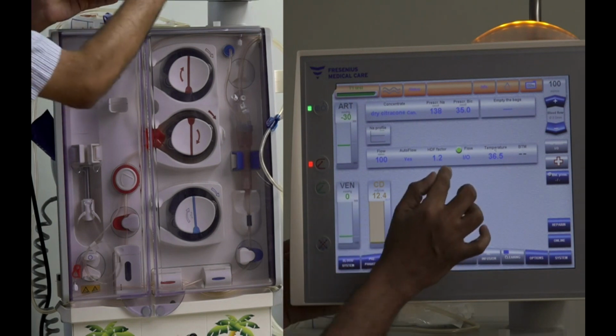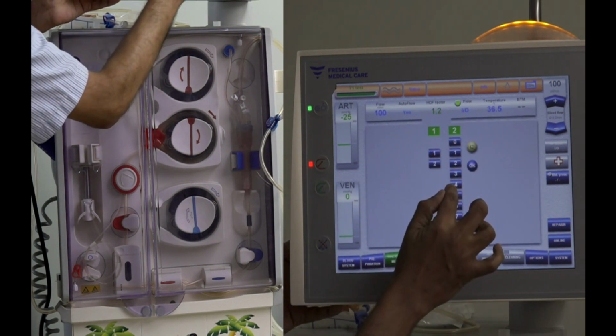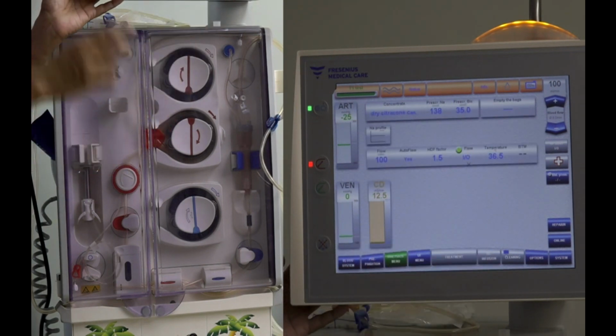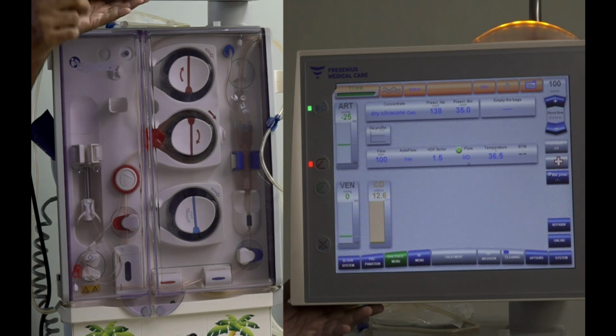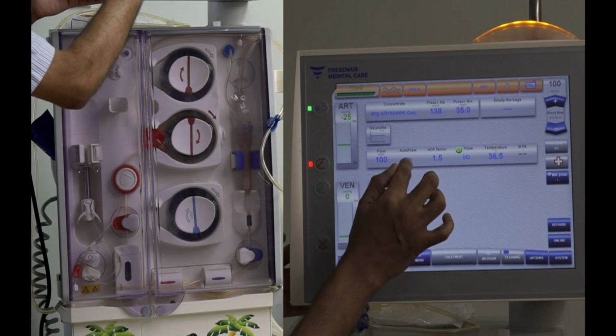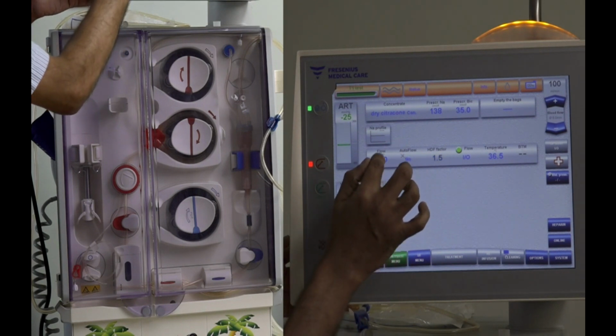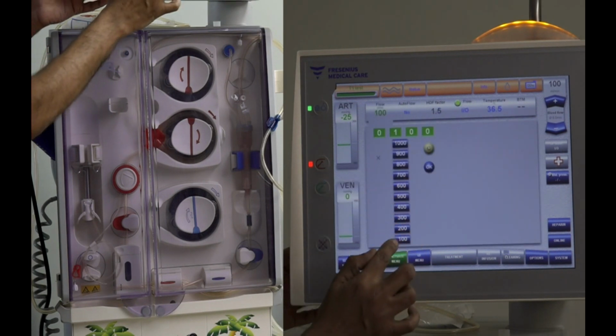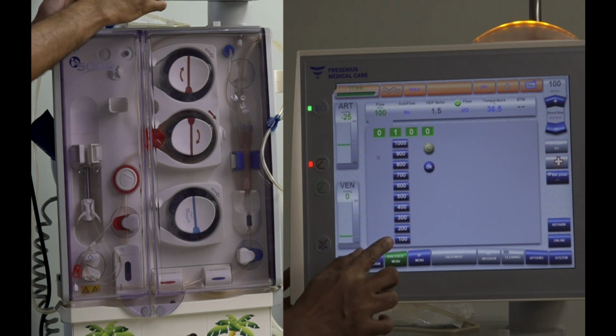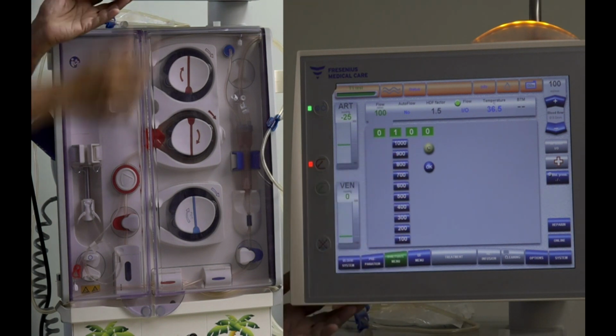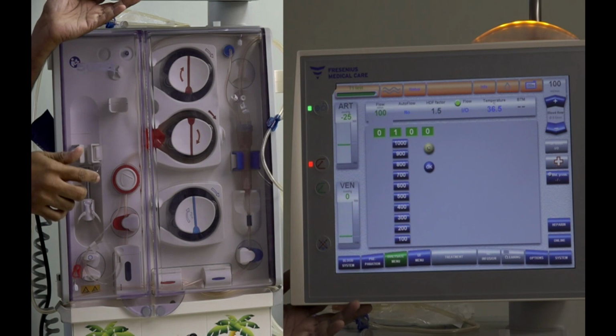We can change this to 1.5, and the dialysate flow will then be kept at 1.5 times the blood flow. If we do not want to use the autoflow option, I switch it off, and then I have an option of setting the dialysate flow from 100 to 1000 ml per minute in increments of 100.